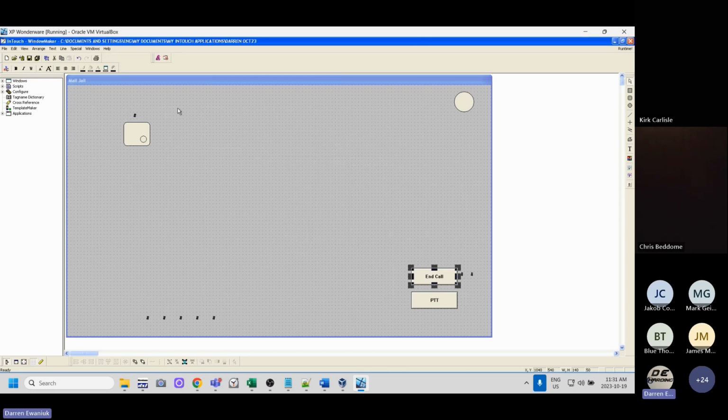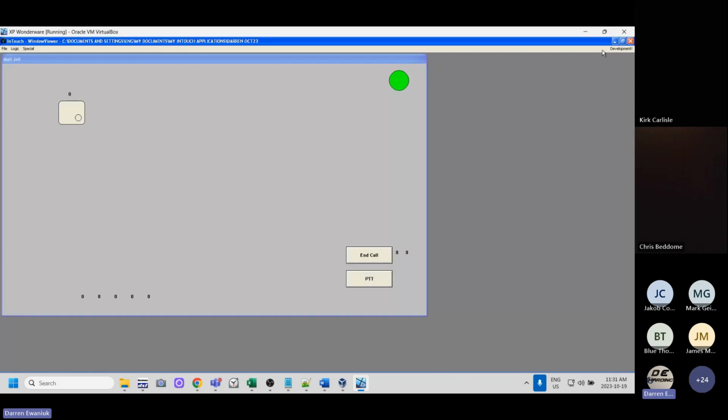All right, so this is going to be very simple. I can't do everything with this right now, but I'll show you. This is the first pass at my system. So I'm going to go and do the runtime. So let's get a run. The first thing I see is my connection status is green. Well, that's good. That means that I am communicating with the DXL system.